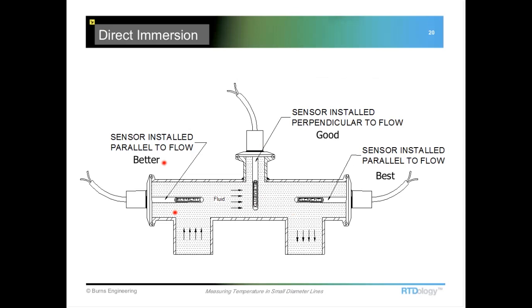Something that would be a little better would be to install it into the run of the T. So we've got the flow coming up here. The one drawback with this type of installation is that you have a little bit of a dead leg back here in a standard pipe T, and this fluid doesn't always get cleaned out very well. And if you're running a CIP system, this is not going to get flushed out very well.